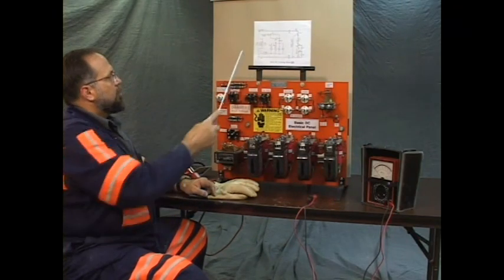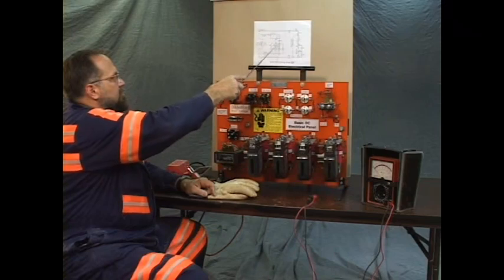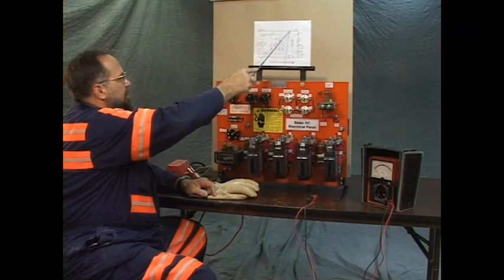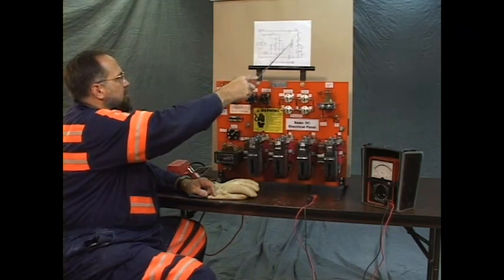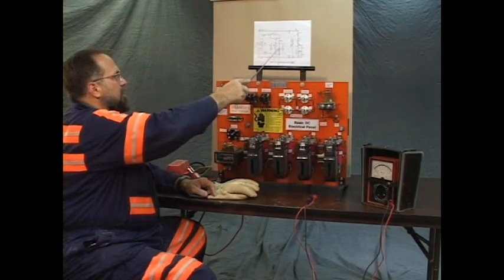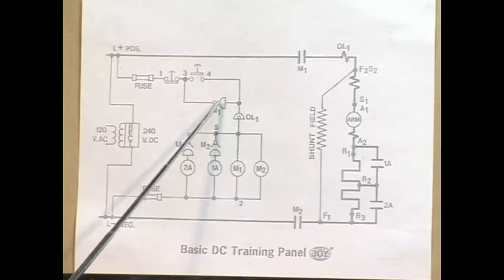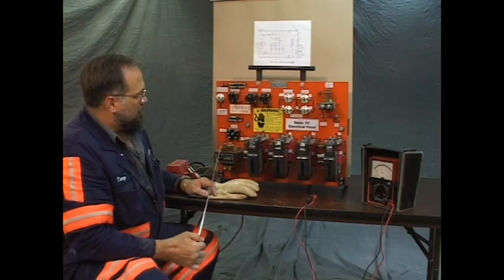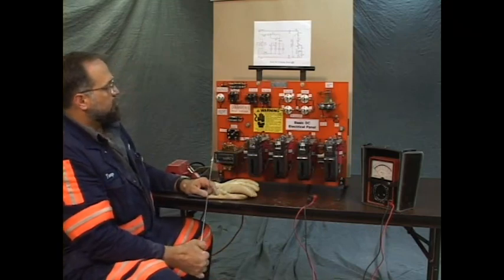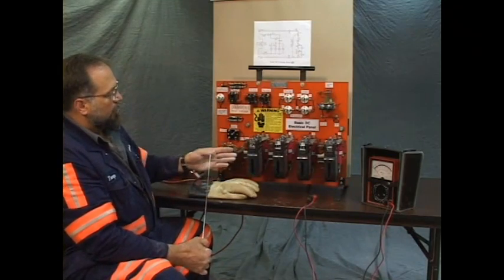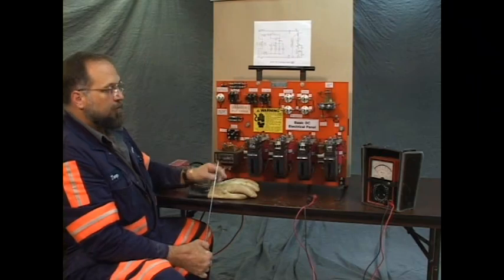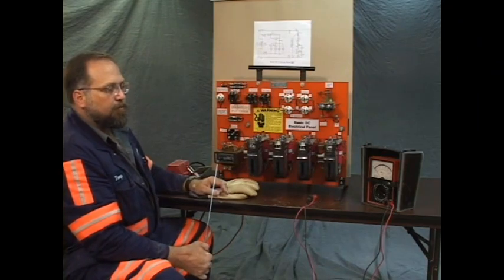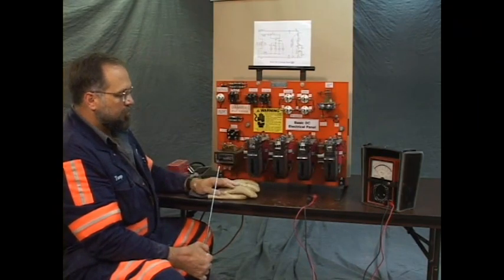When the M1 contactor coil is energized, it becomes a magnet, and it has the effect of closing these contactor tips, supplying positive voltage to this part of the circuit over here. And also, the magnetism is responsible for closing this mercury tube. A mercury tube is one of the first relays that were used, and a mercury tube has mercury in it. Mercury does respond to magnetism.